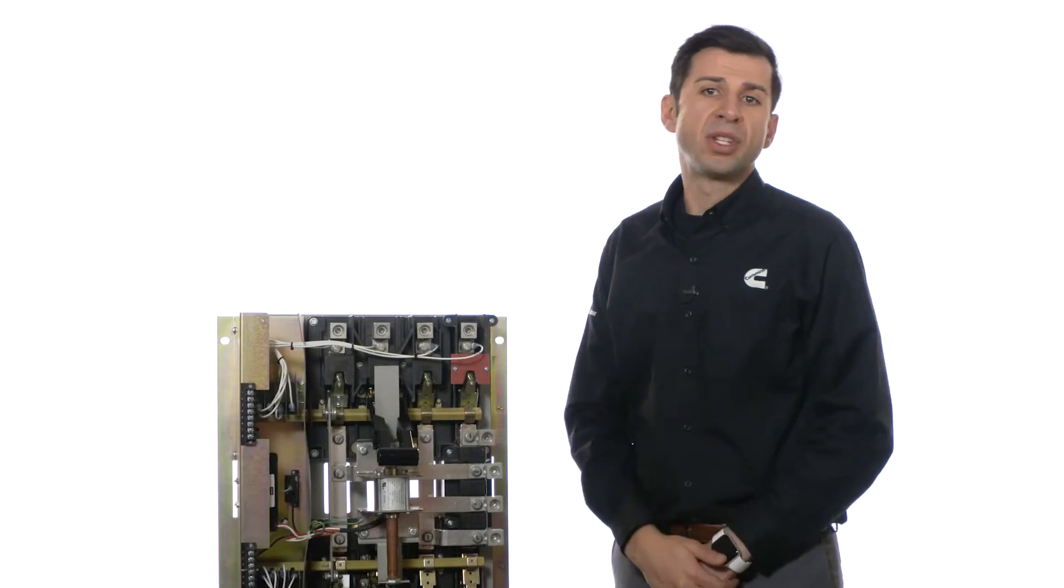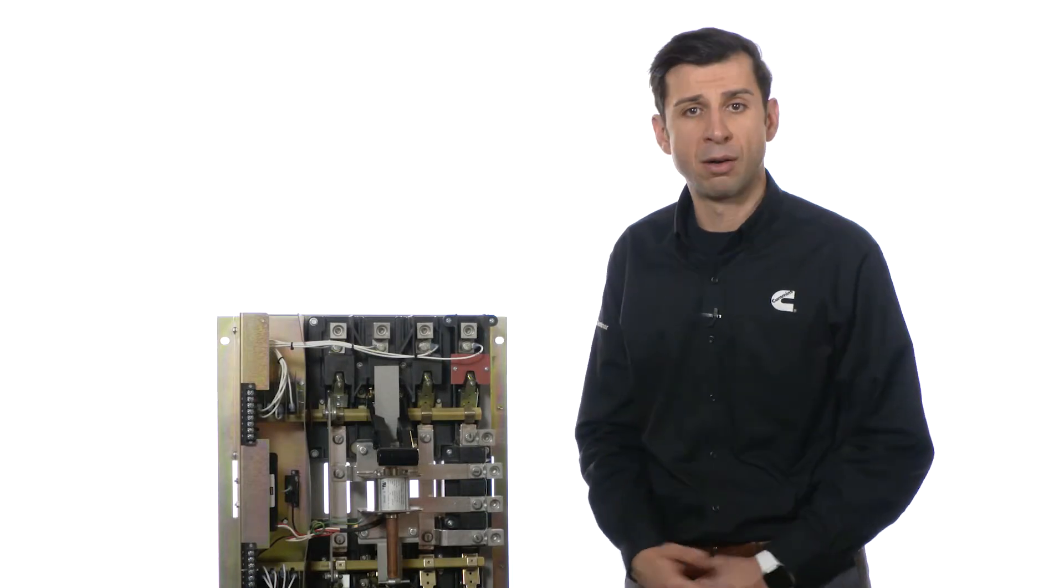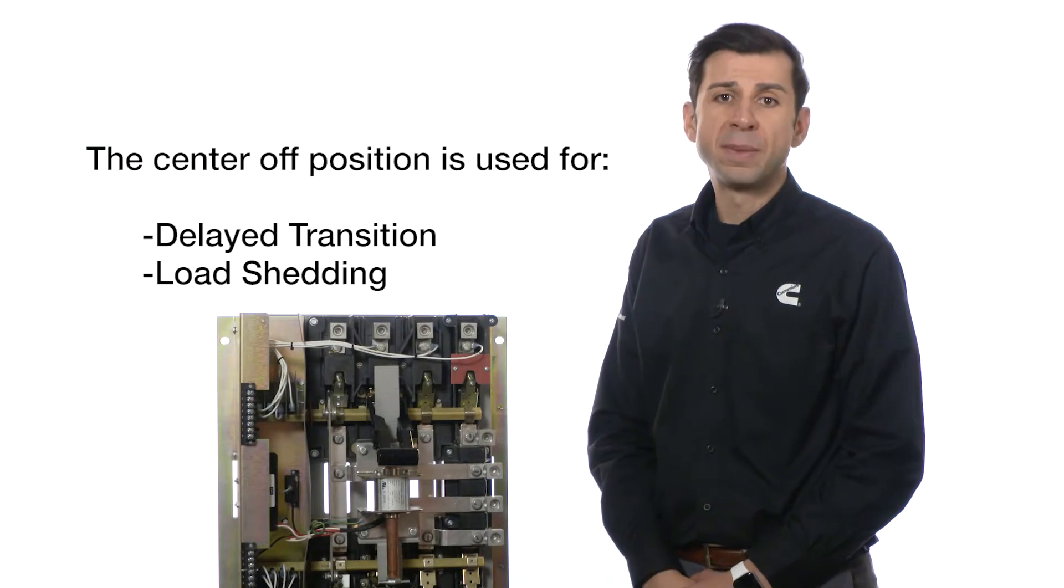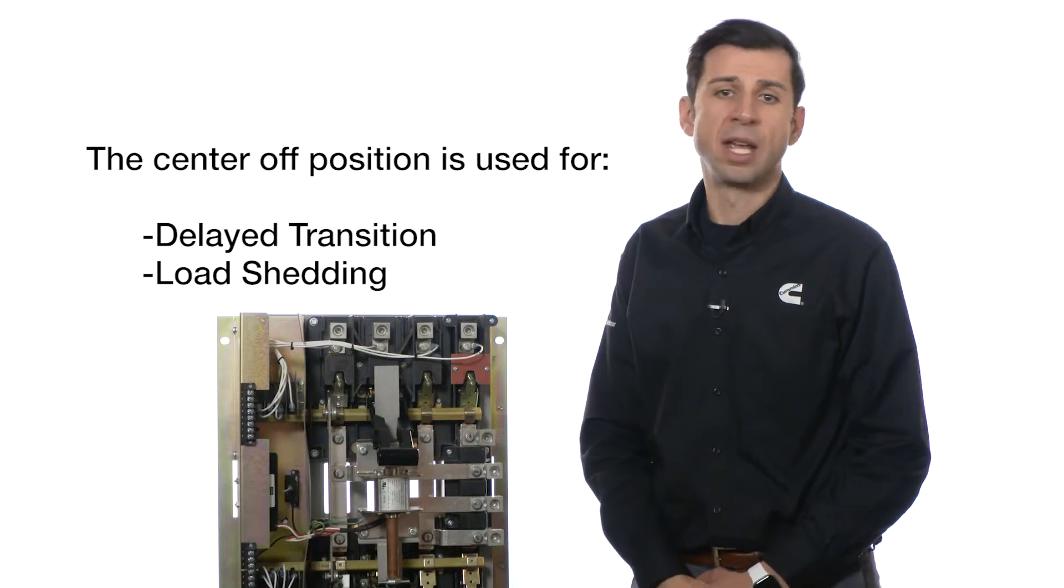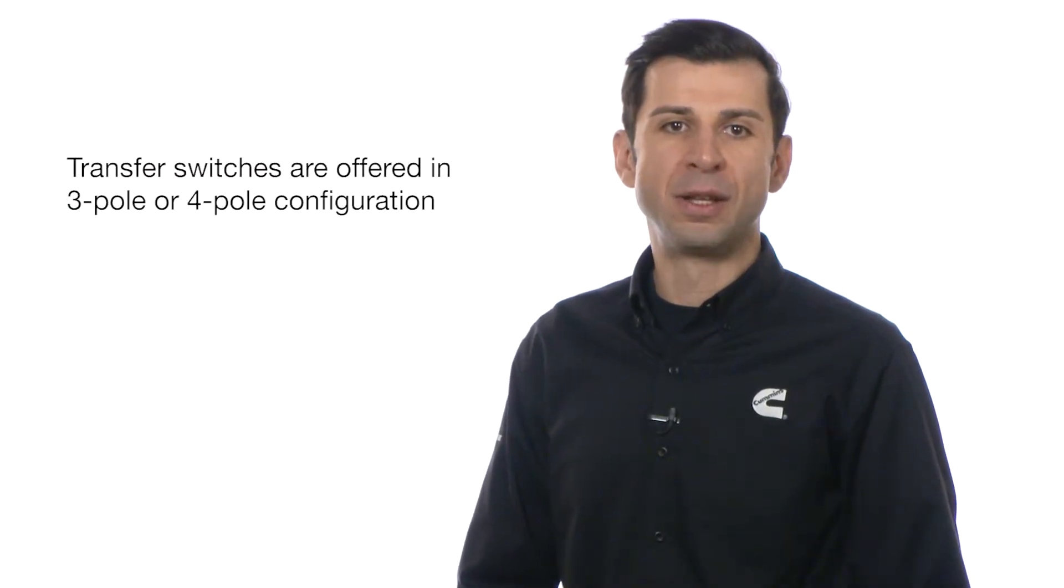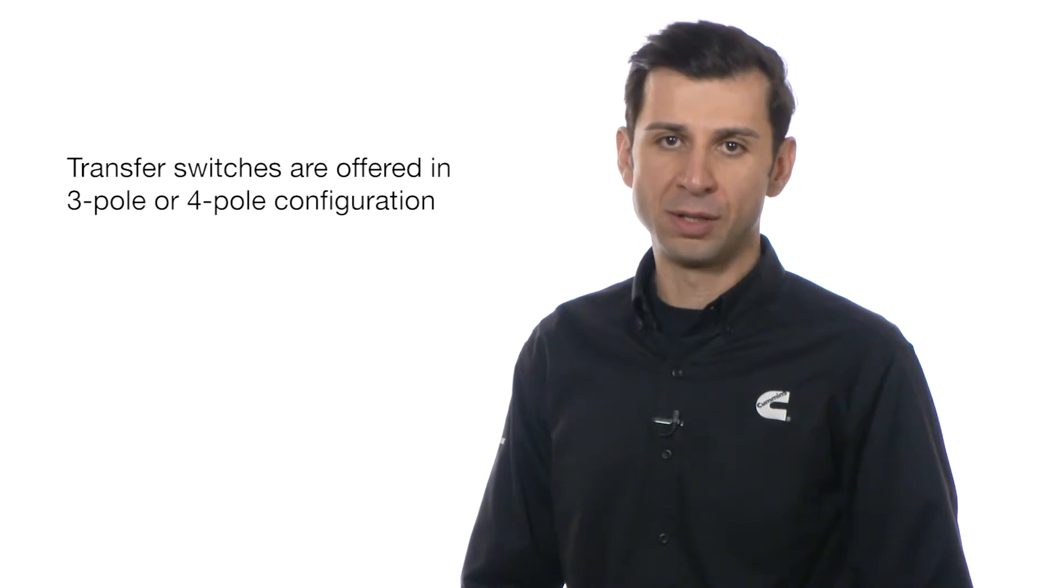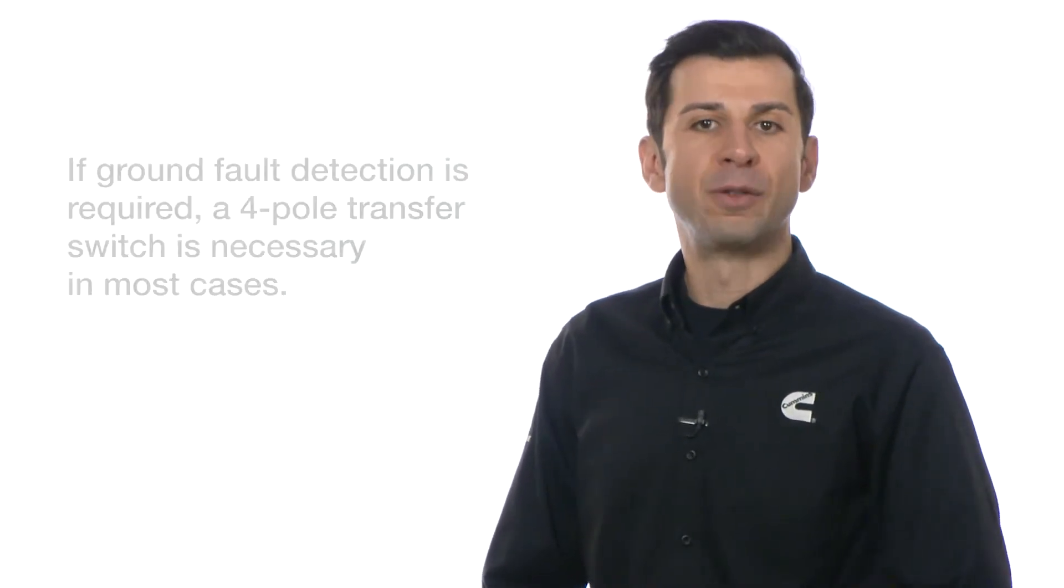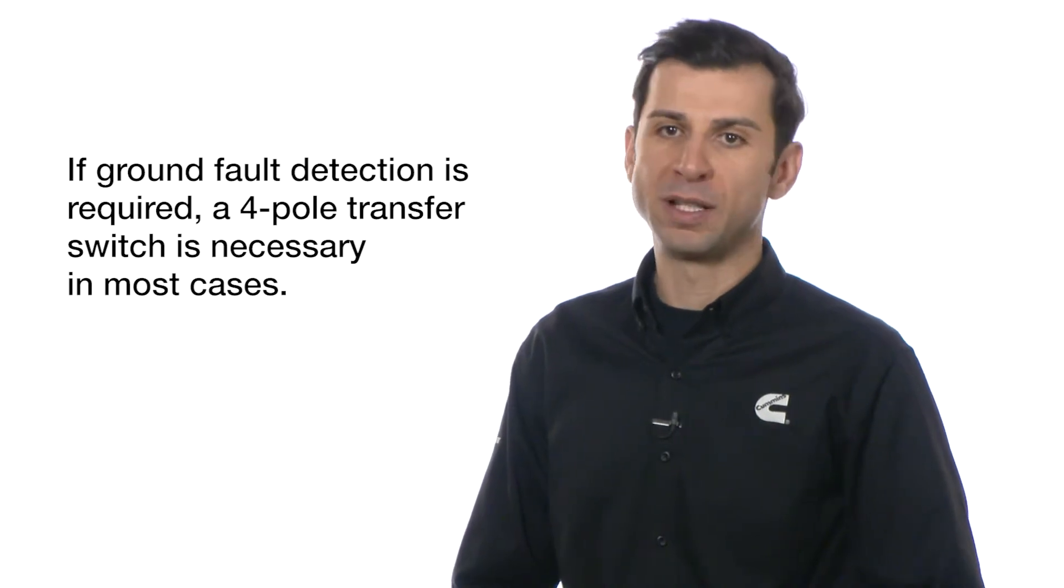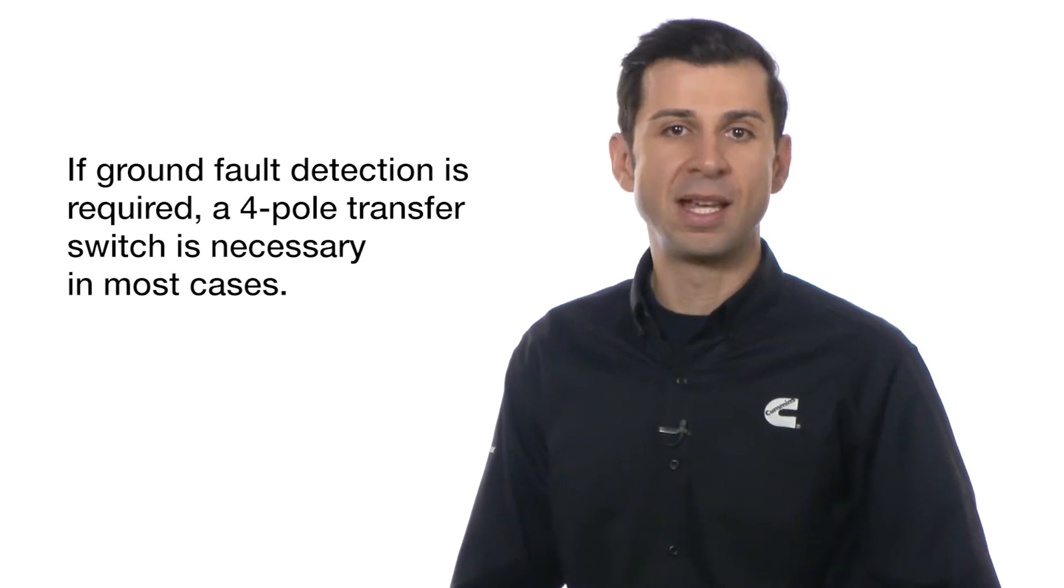There are also two-position transfer switches that do not have a center-off position. The center-off position is used for delayed transitions and load shedding. Since transfer switches are offered in a three-pole or four-pole configuration, to determine which one to select, attention must be paid to the system grounding scheme and ground fault protection requirements. If ground fault detection is required, a four-pole transfer switch is necessary in most cases.